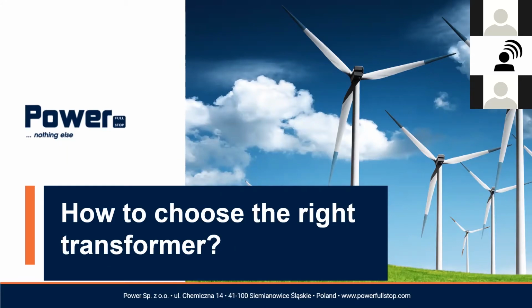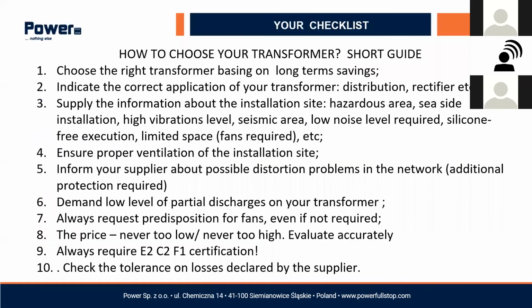In distribution markets, cast resin transformers are really winning a lot of market because of their safety. They can be installed inside buildings, and there's no problem with fire, etc. But for some applications, when we see that the costs of a cast resin transformer exceed oil transformers too much, we also invite our clients to consider buying an oil transformer instead. So this list is based, of course, on cast resin transformers.